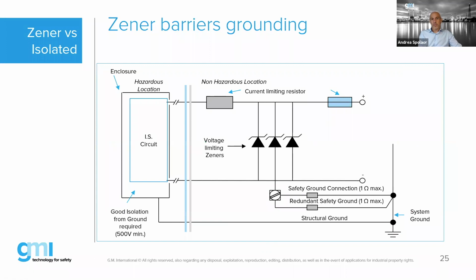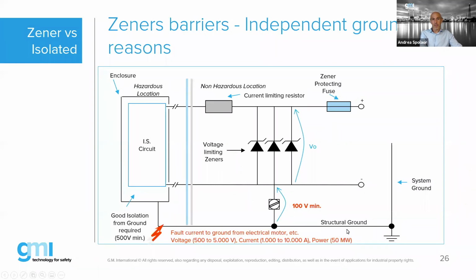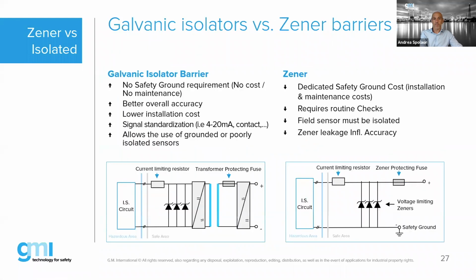And this is the grounding that you also have to ensure when you install a Zener barrier. There is a safety ground for the barriers, which can also be a redundant safety ground. And the ground for the enclosure where the field sensor is installed must also be connected. This is a basic wiring. Sometimes you have fault current to ground from electrical motors, and this fault from the hazardous area will go to the Zener barriers, which is also a dangerous situation. A slide that gives you details.